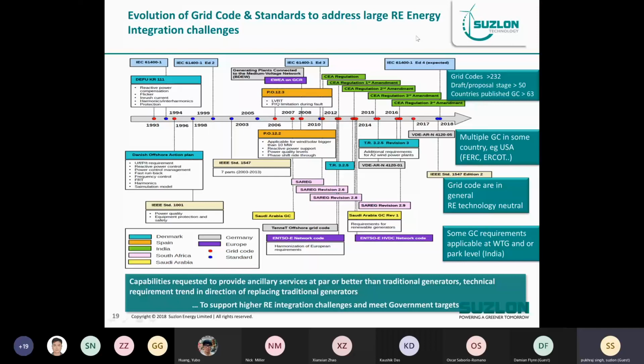Whether it's IEC standards or IEEE standards, I see IEC standards are sometimes a bit slow. The IEEE standard for harmonics, IEEE 519, was first published around 1995, and the second revision came in 2014 - after 15 years. But grid codes change quite fast. Take South Africa as an example - every year they change requirements and ask us to keep our plants compliant with the upcoming grid codes. This is a big challenge. Even if I install turbines today, I don't know what the requirements will be after 2 years. So we have to forecast and do research on what kind of requirements may come, which we should consider today.